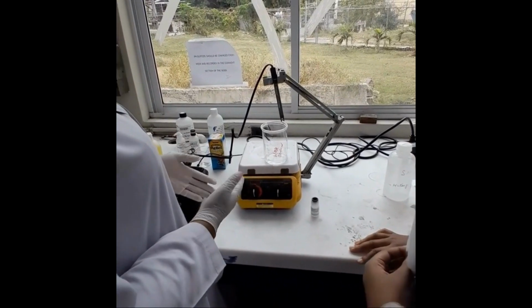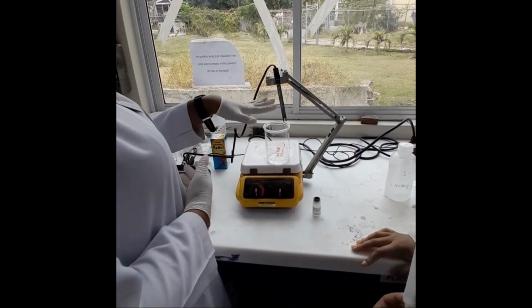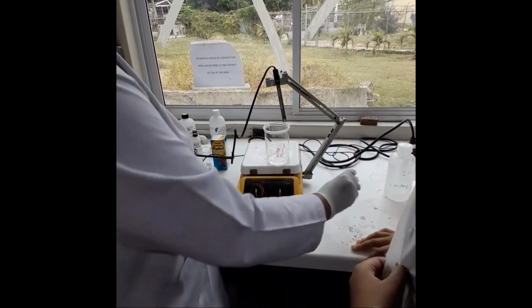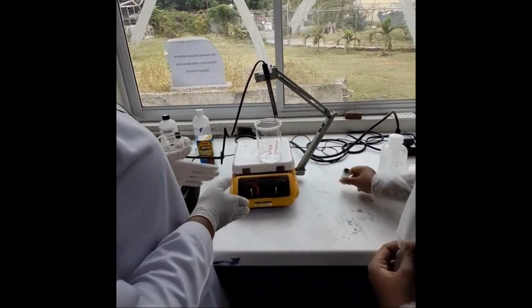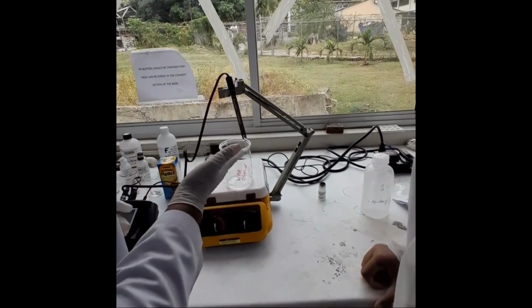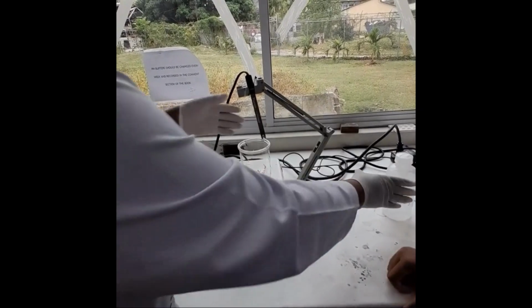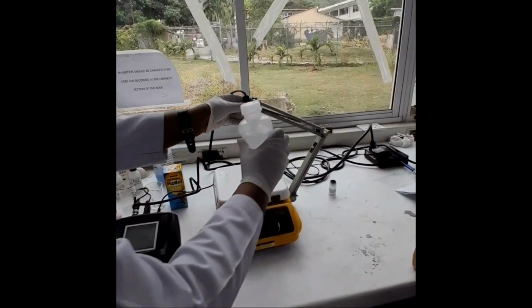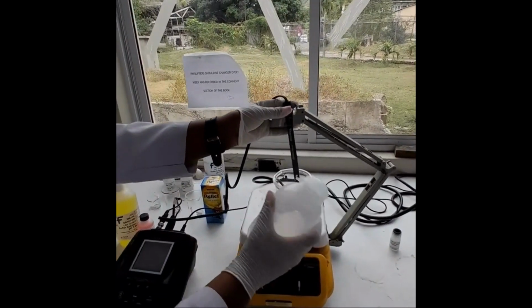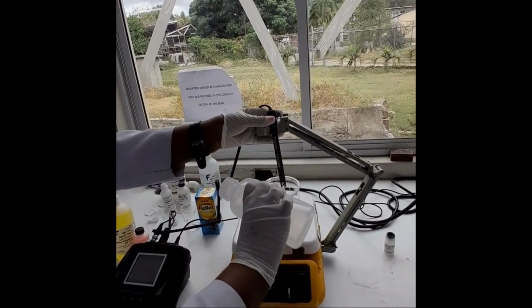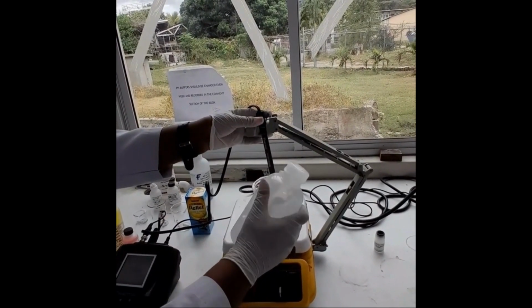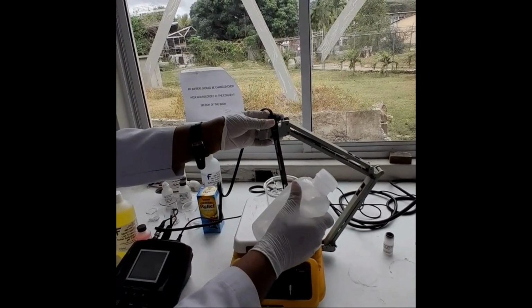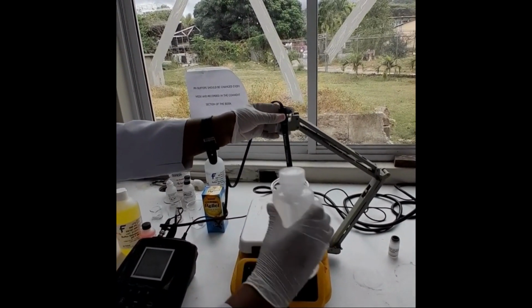To calibrate now, first we are going to remove our storage solution, but you put it away securely, you don't want the solution to be thrown away. And you're going to rinse your probe with distilled water. You want to rinse especially down here where the sensor is on the probe. All right, so that would be good.